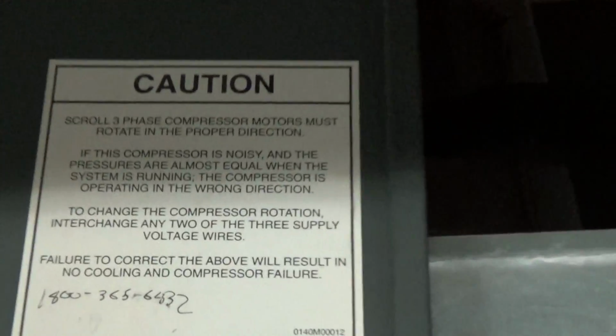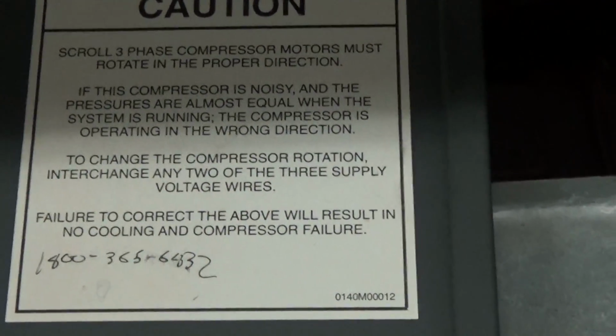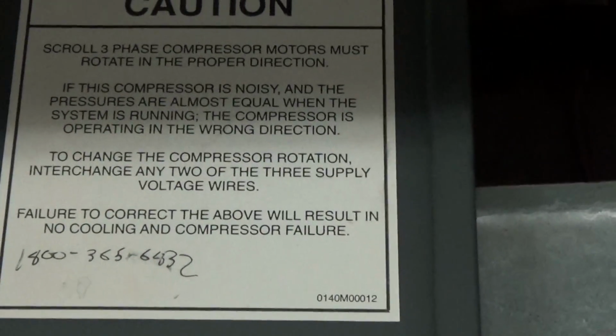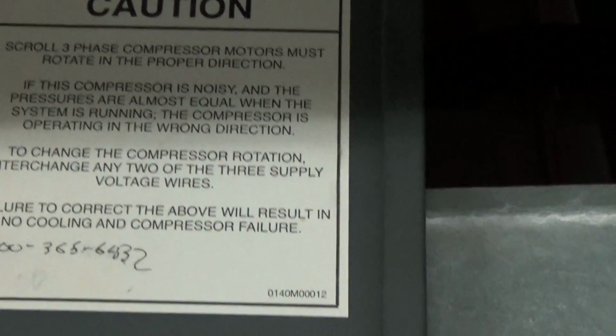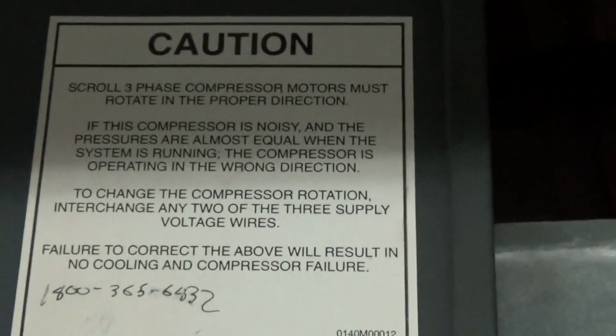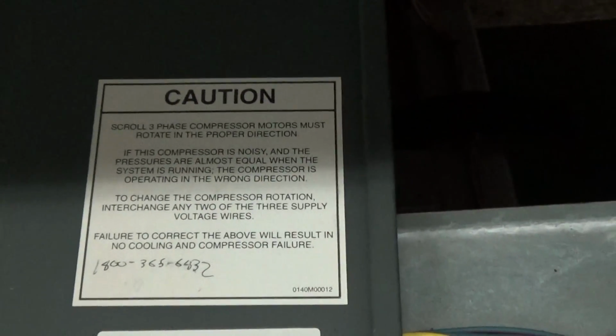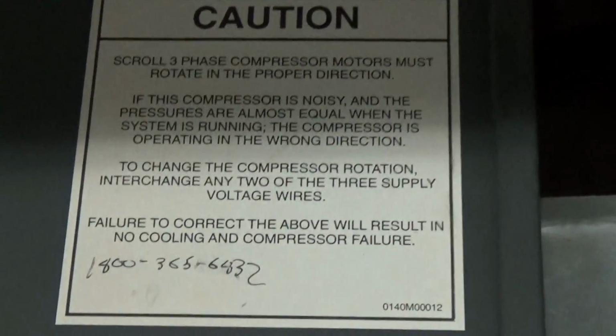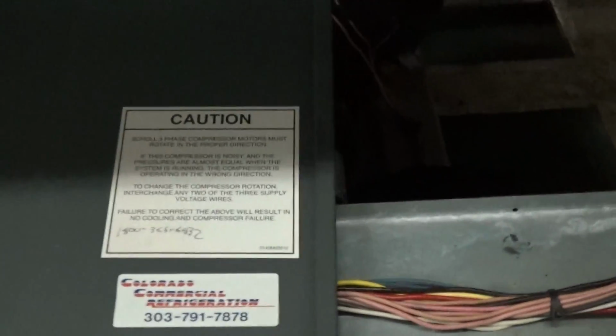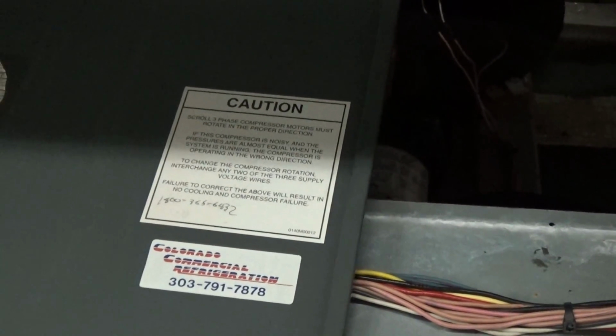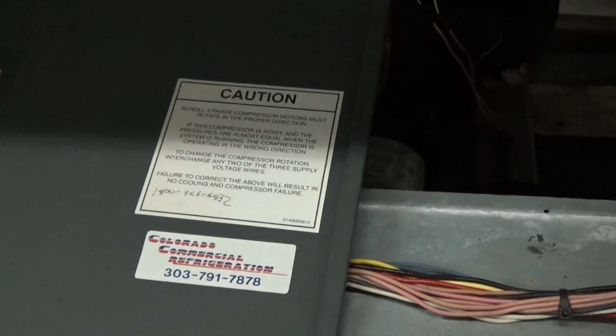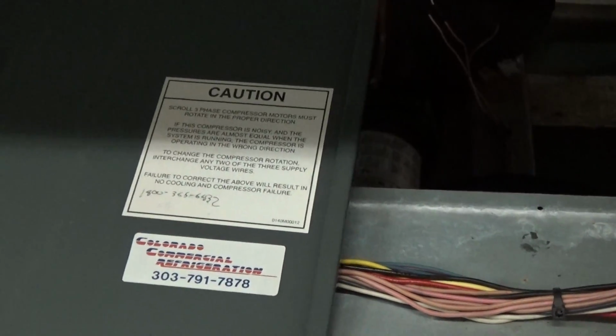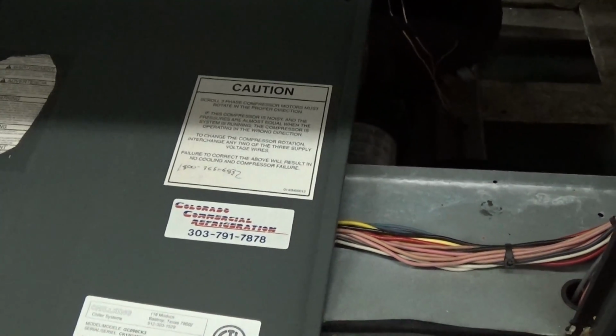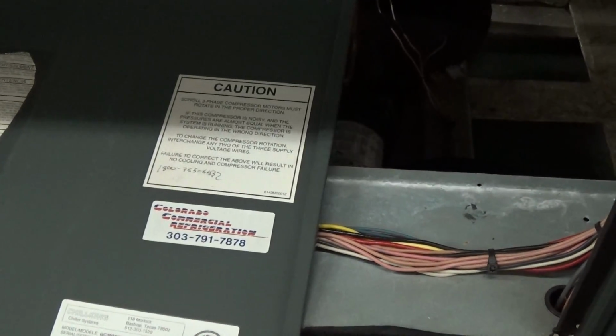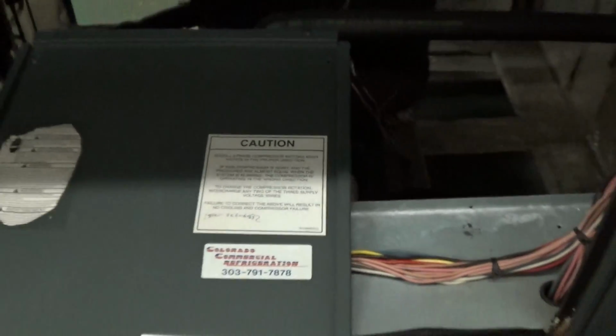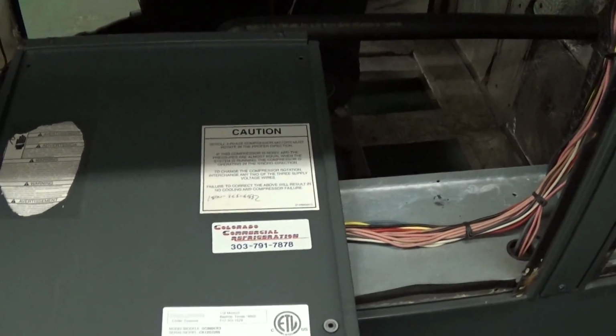To do that, the technician would put his gauges on the unit, and the way they say it here on the label is this: if the compressor is noisy and the pressures are almost equal when the system is running, the compressor is operating in the wrong direction. And that is true. But on the initial startup, have an HVAC technician here just to confirm the rotation. The last thing you want to do is run those compressors in reverse, and some people can make the mistake, if they see the fans rotating in the right direction, of thinking everything is hunky-dory. That's not the case, because it's single-phase fans and a single-phase pump.